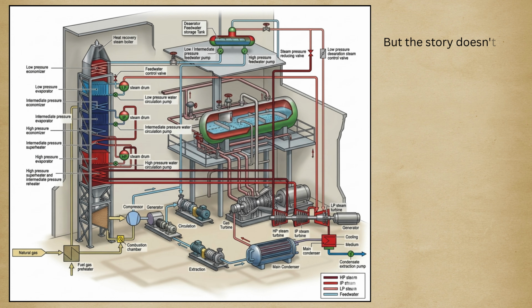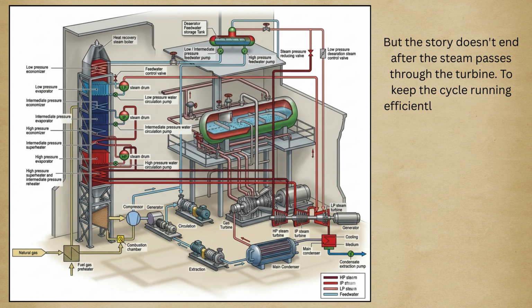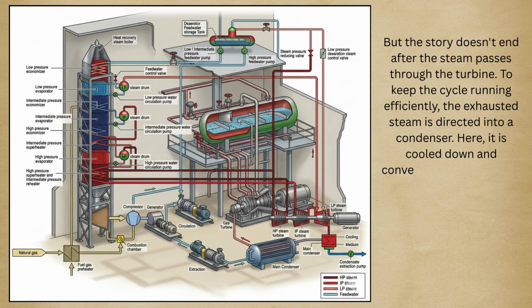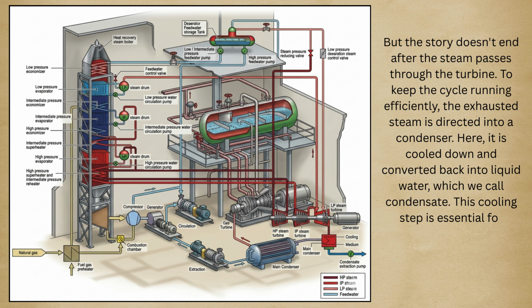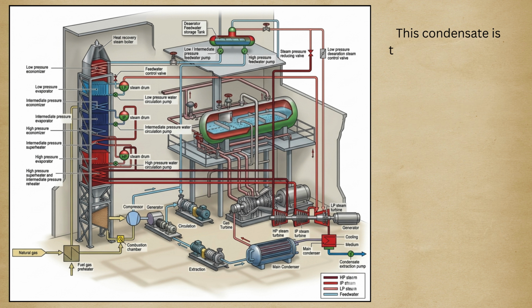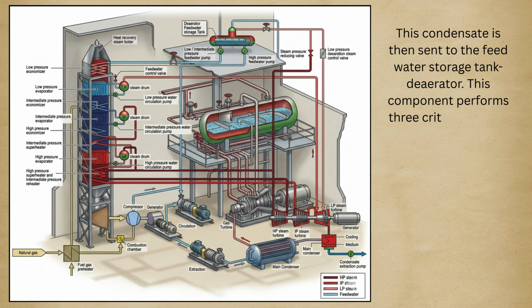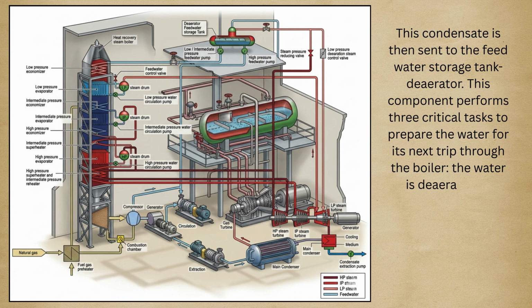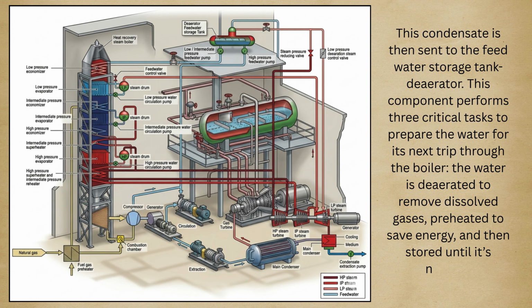But the story doesn't end after the steam passes through the turbine. To keep the cycle running efficiently, the exhausted steam is directed into a condenser. Here, it is cooled down and converted back into liquid water, which we call condensate. This cooling step is essential for maintaining the pressure balance of the entire system. This condensate is then sent to the feed water storage tank deaerator. This component performs three critical tasks to prepare the water for its next trip through the boiler. The water is deaerated to remove dissolved gases, preheated to save energy, and then stored until it's needed.